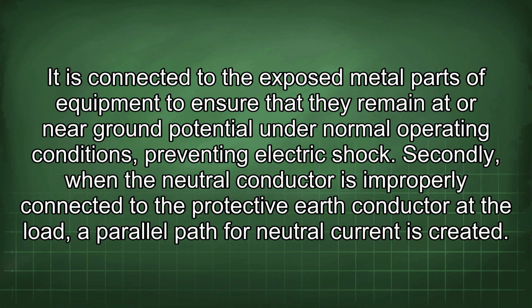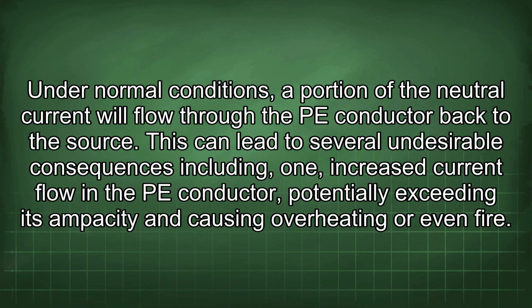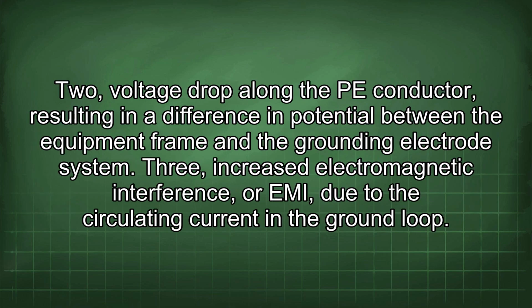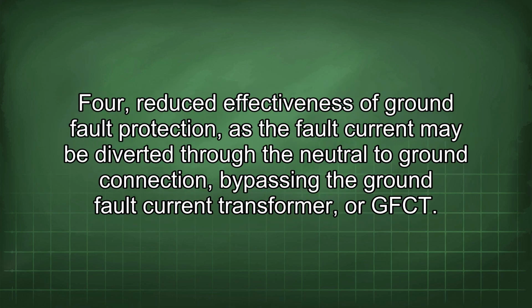Secondly, when the neutral conductor is improperly connected to the protective earth conductor at the load, a parallel path for neutral current is created. Under normal conditions, a portion of the neutral current will flow through the PE conductor back to the source. This can lead to several undesirable consequences, including: 1. Increased current flow in the PE conductor, potentially exceeding its ampacity and causing overheating or even fire. 2. Voltage drop along the PE conductor, resulting in a difference in potential between the equipment frame and the grounding electrode system. 3. Increased electromagnetic interference, or EMI, due to the circulating current in the ground loop. 4. Reduced effectiveness of ground fault protection, as the fault current may be diverted through the neutral to ground connection, bypassing the ground fault current transformer, or GFCT.